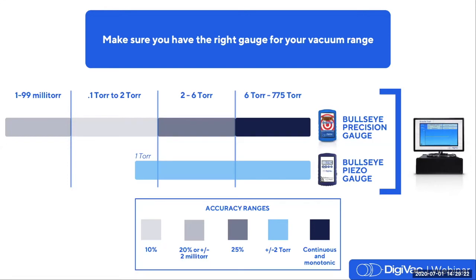From 2 to 6 torr, our accuracy range is 25% of reading. Between 6 torr and 775 torr, we call this range continuous and monotonic, meaning that the readings will change, and they will change in one direction, but they're not repeatable and can vary a significant amount from the standard. So we don't give an accuracy spec to this range in particular. We consider our range with accuracy below 6 torr.